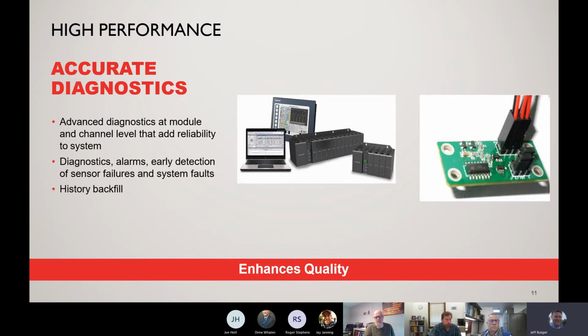The other big thing is that it has a history backup. For example, if this HC900 were communicating to a SCADA supervisory software package, and the communications between this rack and the software were to fail, once it becomes live again and everything's back up and running, the HC900 will take all of the history data with the trend charts and things of that nature, and backfill all those data points into the SCADA so that you don't have any missing data. It has onboard memory on the CPU that allows that history to be stored on the CPU for later retrieval.